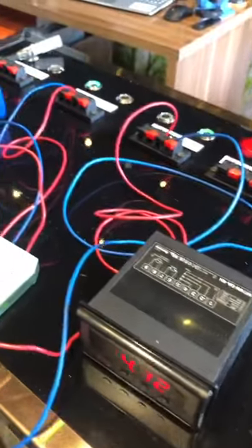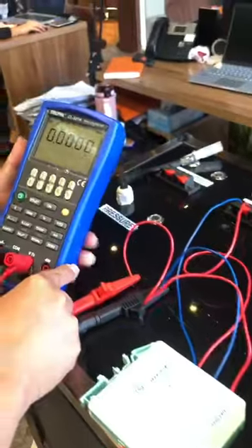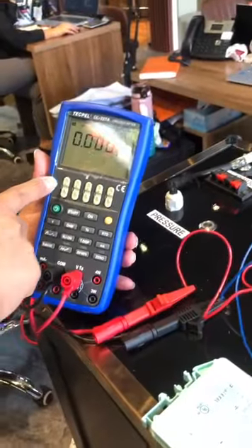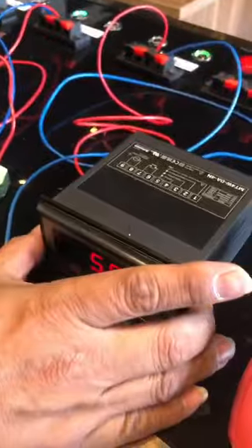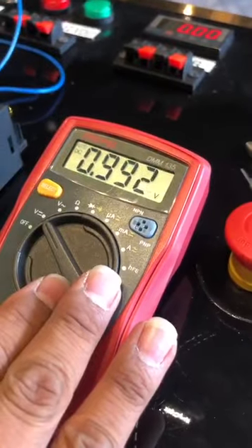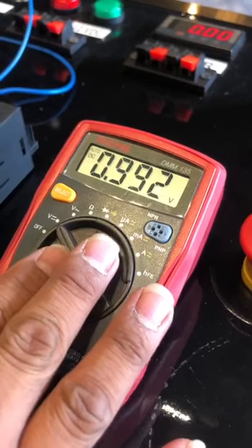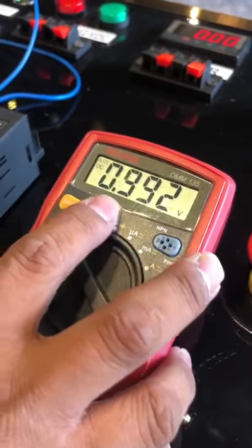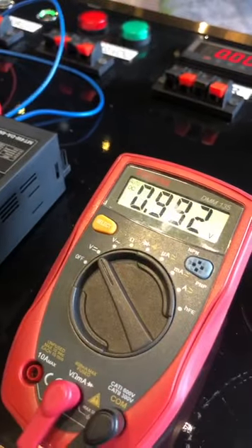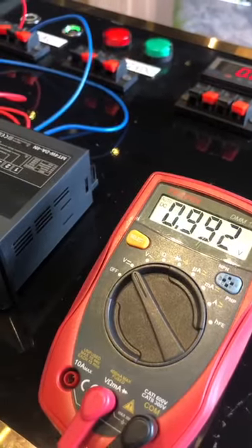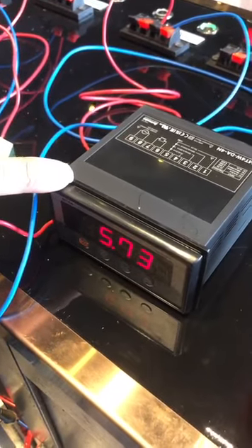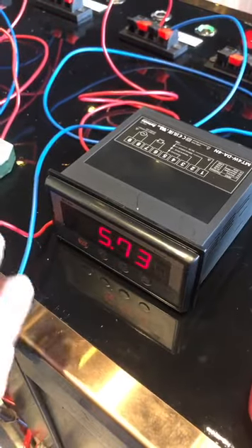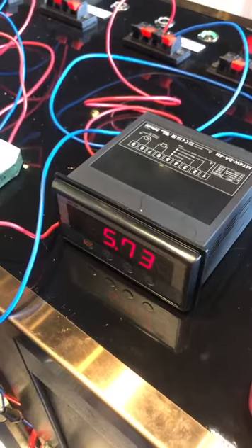As you can see right now, if I start to simulate the voltage, let's say I inject 1 volt, our meter will respond accordingly. We have the second output, output number 2, which is set to 0 to 10 VDC output, so you'll get 0.99 volts, which is almost equivalent to 1. While the first output, as we configured it for 4 to 20 milliamps, is giving us 5 milliamperes, which is almost equivalent to the 1 volt input signal.